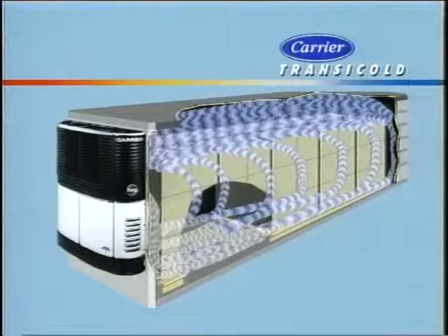Fifteen seconds after the engine starts, either the heat or cool light will come on to show which mode the unit is operating in. You always need to check with your dispatch or road department for guidance on where the unit should be set for each individual load. As we mentioned earlier in the program, the set point can be adjusted from -22 degrees Fahrenheit to +89.6 degrees Fahrenheit. This particular trip calls for a set point of -22 degrees Fahrenheit and start-stop operation.